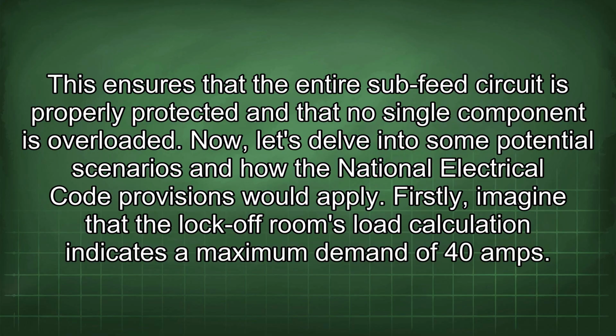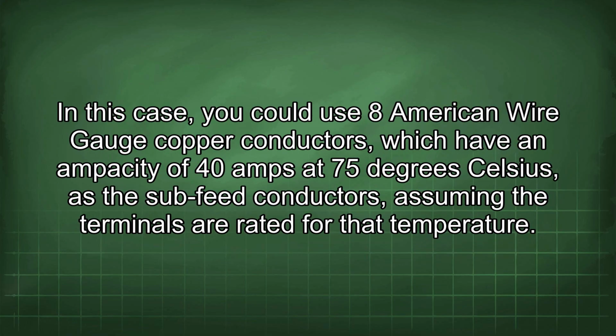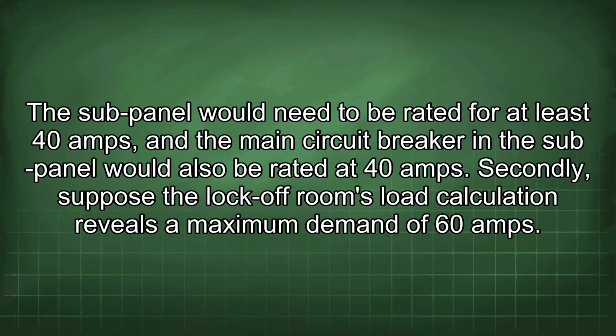Now let's delve into some potential scenarios and how the National Electrical Code provisions would apply. Firstly, imagine that the lock-off room's load calculation indicates a maximum demand of 40 amps. In this case, you could use 8 American wire gauge copper conductors, which have an ampacity of 40 amps at 75 degrees Celsius, as the sub-feed conductors, assuming the terminals are rated for that temperature. The sub-panel would need to be rated for at least 40 amps, and the main circuit breaker in the sub-panel would also be rated at 40 amps.